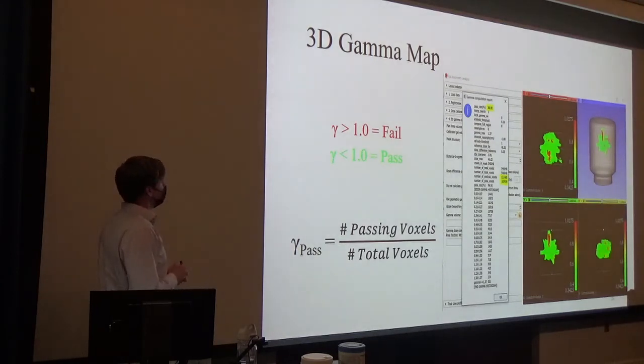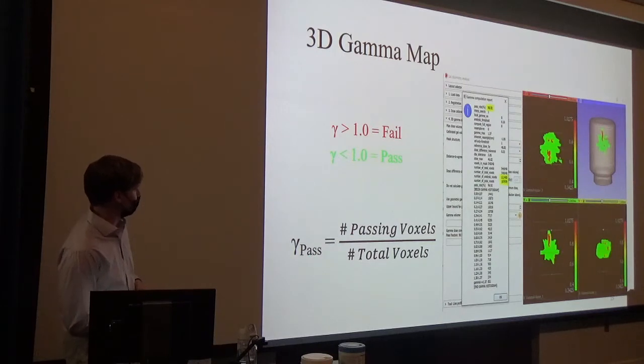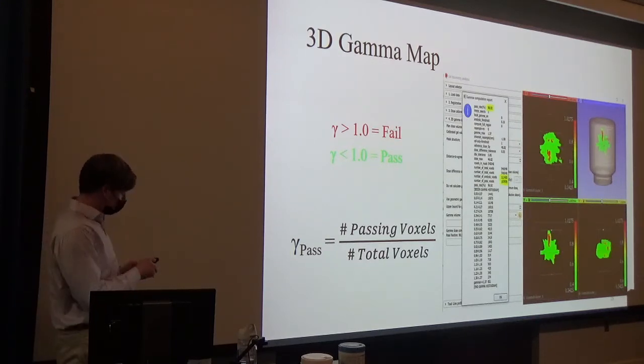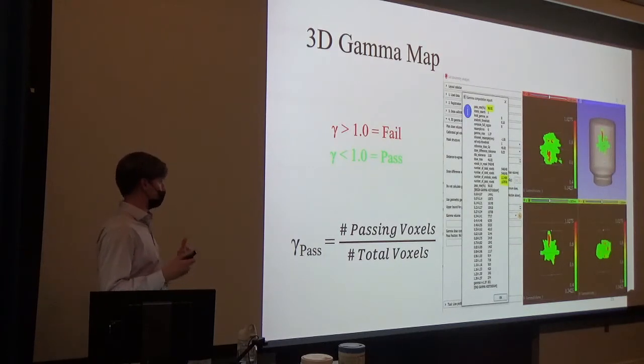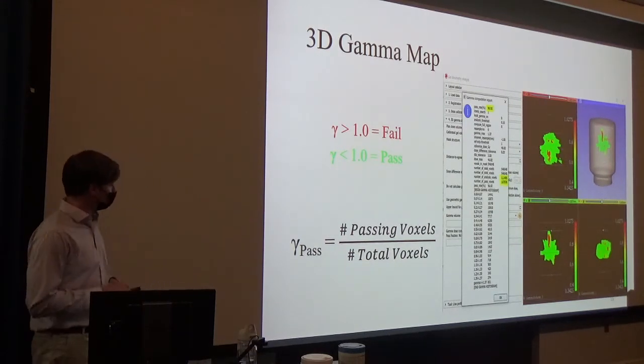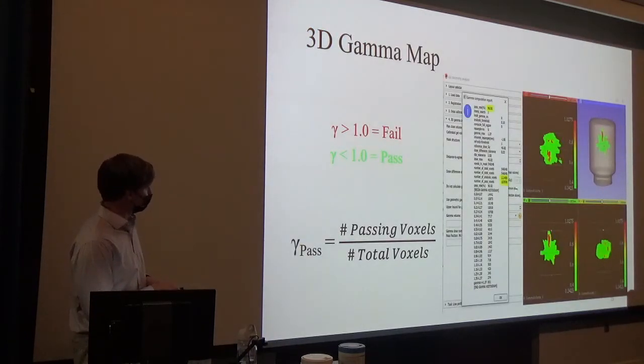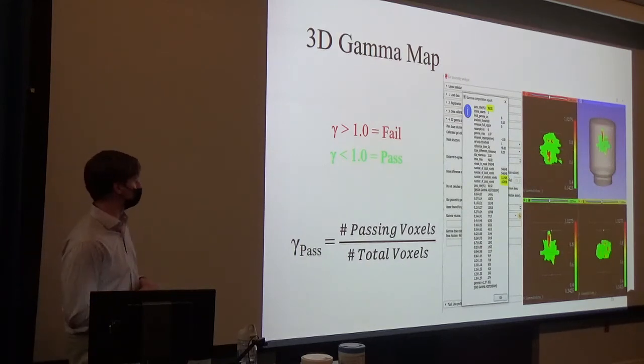We receive a 3D gamma map looking something like this. To get the gamma pass rate, we take the number of passing voxels over the total number of voxels to get our gamma value — in this case 96.92%, which is really good. Greater than one fails, less than one passes. You can see we get some spatial information as to where we passed and where we failed. It's also important to note that this one calculation is being repeated over a hundred thousand times, which illustrates the computational power needed to perform this analysis.